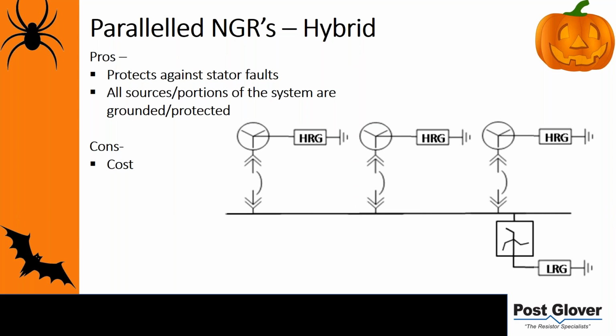So if you just want to have all the maintenance taken care of, and no matter what you do with your configuration, you always have ground fault protection, that's one reason to use the hybrid, but also it's for that generator protection as well. Because you're having, for this example, 4 different resistors, a lot of times this is going to be at 15 kV. So there's going to be extra cost here. So that's the negative here. You're going to be 2 to 3 times more than just your typical LRG, and then maybe twice as much as if you did one per generator.